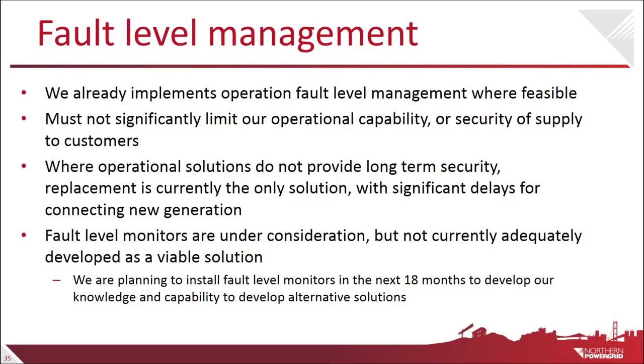We are looking at ways to try to manage fault level. Active network management is something that we use for thermal issues. At the moment we don't see it practically being applied for fault level, but we are planning to install some fault level monitors over the next 18 months so that we can compare our measured actual values on site with our theoretical values in our models, and then we can look at whether there is actually any scope for offering customers solutions that might allow them to connect when theoretically the fault level might be bust.